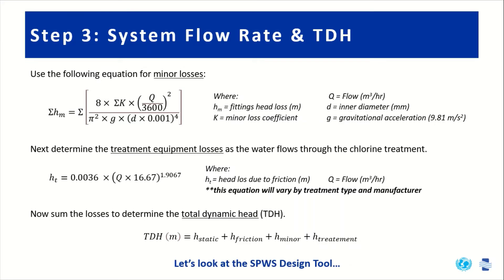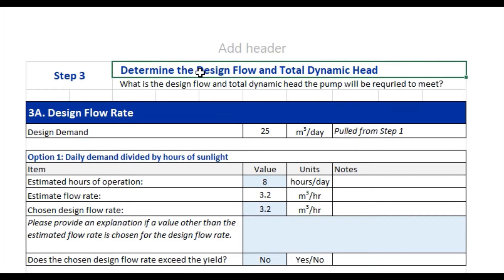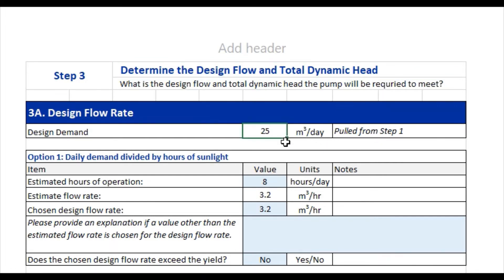Now we've arrived at step three in our solar-powered water system design tool, where we will determine the design flow and total dynamic head. The design demand pulled from step one was about 25 cubic meters per day. Next, we enter the estimated hours of operation for the specific project location, based on estimated hours of peak sunlight. In this case it was eight hours per day, though this varies by location. The design tool then estimates the flow rate by dividing design demand by estimated hours of operation, giving us 3.2 cubic meters per hour.